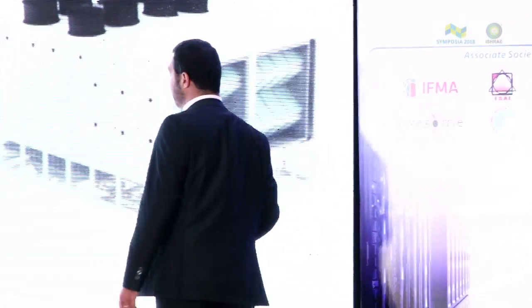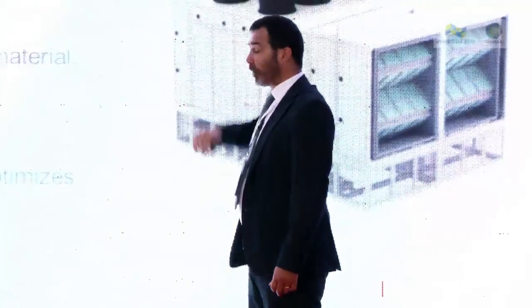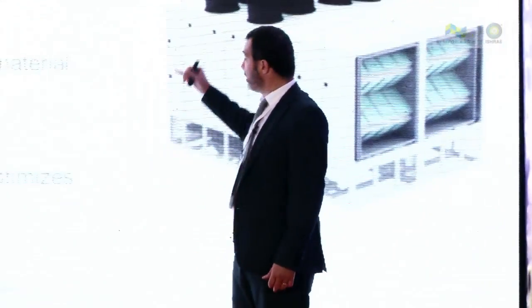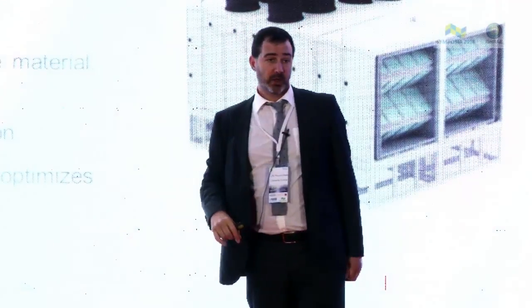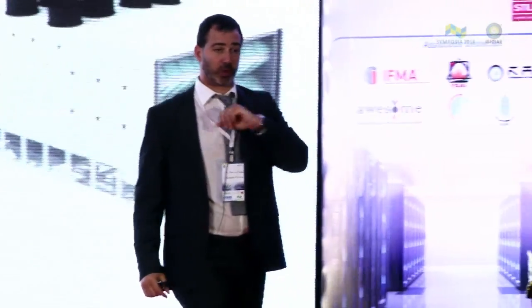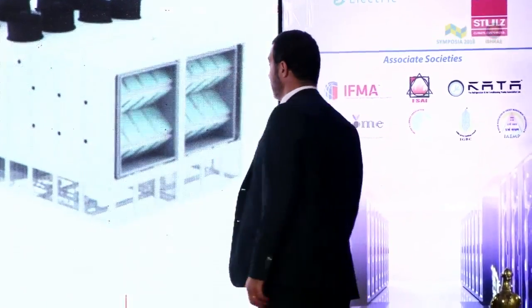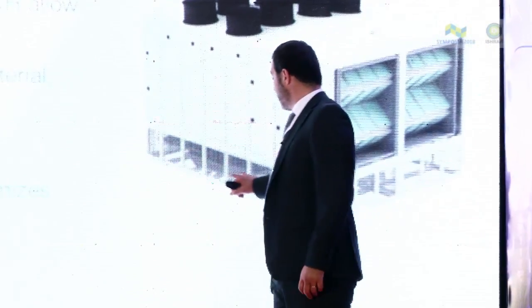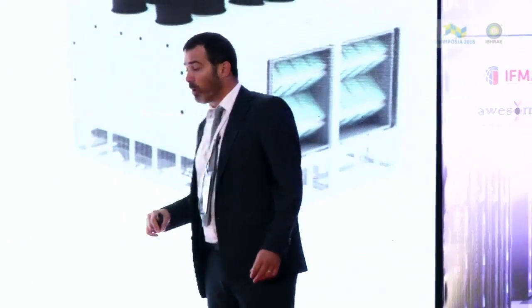It keeps wet. This water evaporates. By means of the evaporation, the load is dissipated. If this is enough, the air temperature here is at the set point. If this is not enough, then here there is a coil which dissipates the last part of the cooling. Then the water that is not evaporated is collected here and then recirculated. So part of the water is wasted, used, part of the water is recirculated.